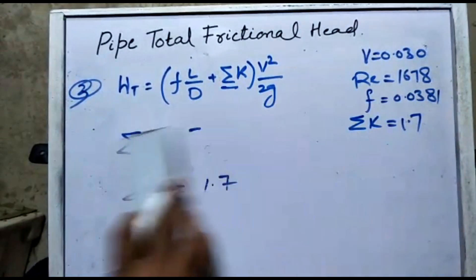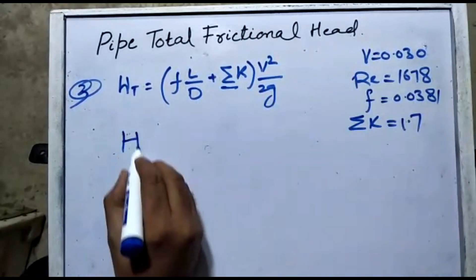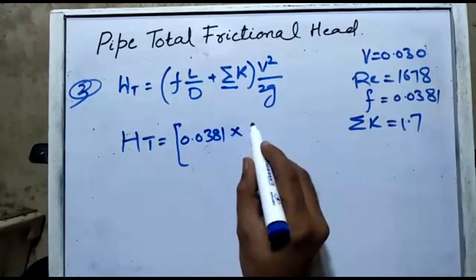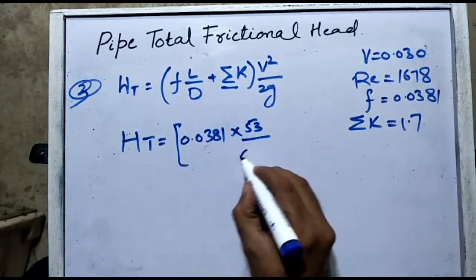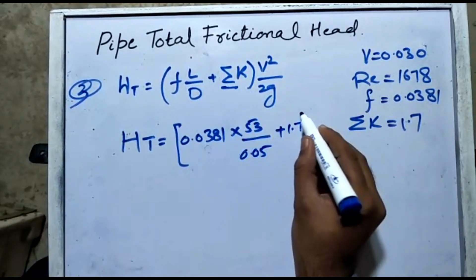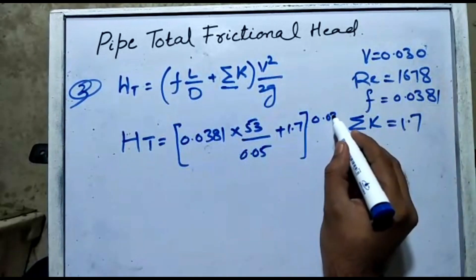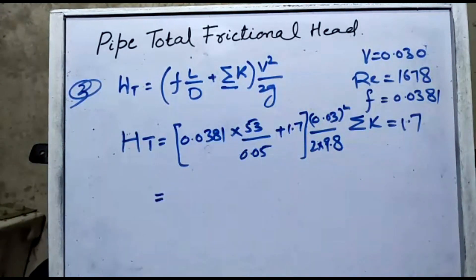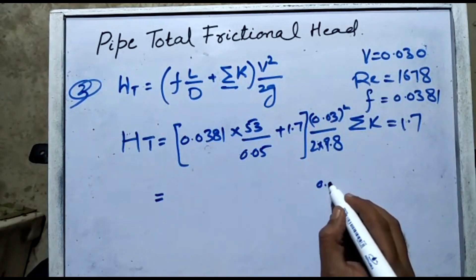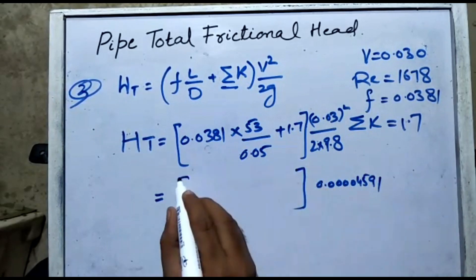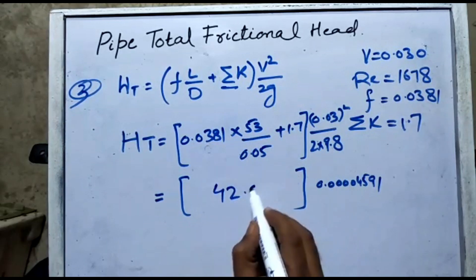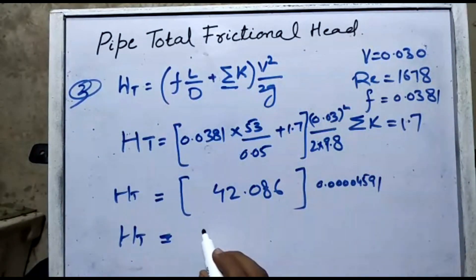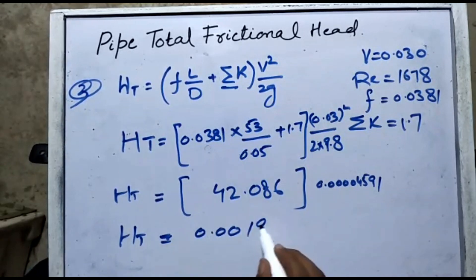All values are now known: f = 0.0381, L = 53 m, d = 0.05 m, ΣK = 1.7, v = 0.03 m/s, g = 9.8 m/s². Computing the bracket: (0.0381 × 53/0.05 + 1.7) = 40.386 + 1.7 = 42.086. Then multiplying by v²/2g: 0.03²/(2 × 9.8) = 0.0000459. This gives a total frictional head of approximately 0.00193 m.